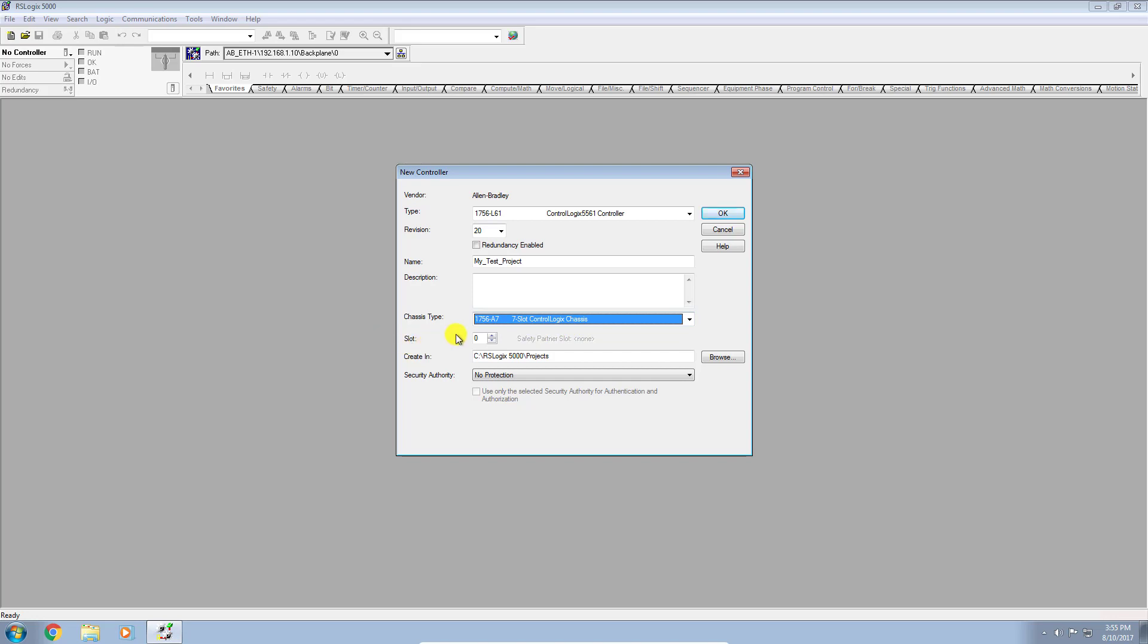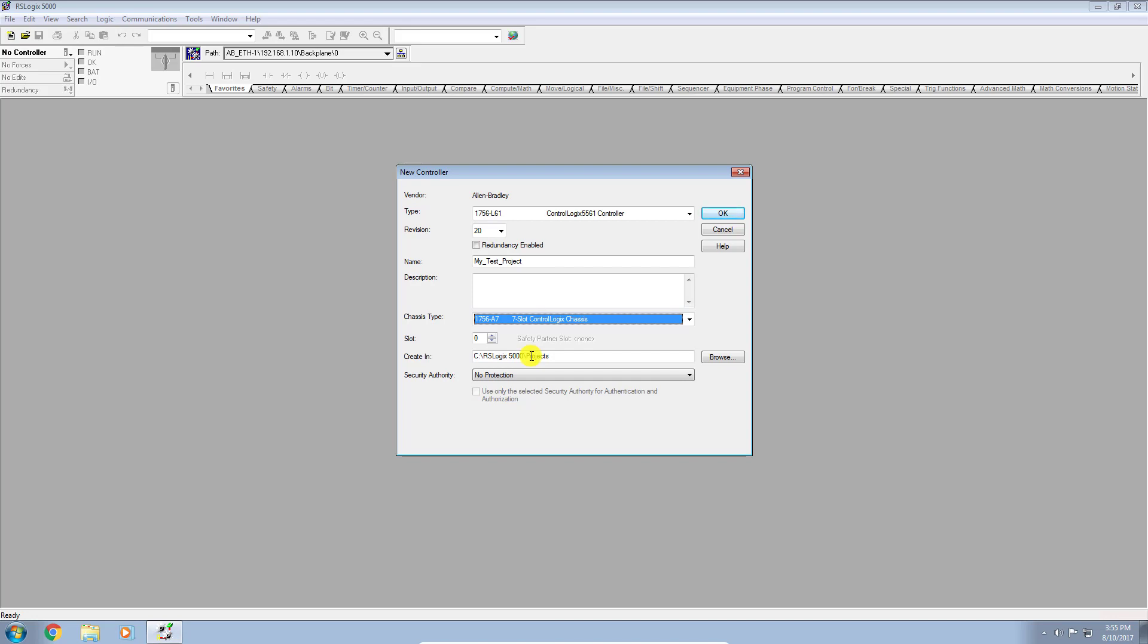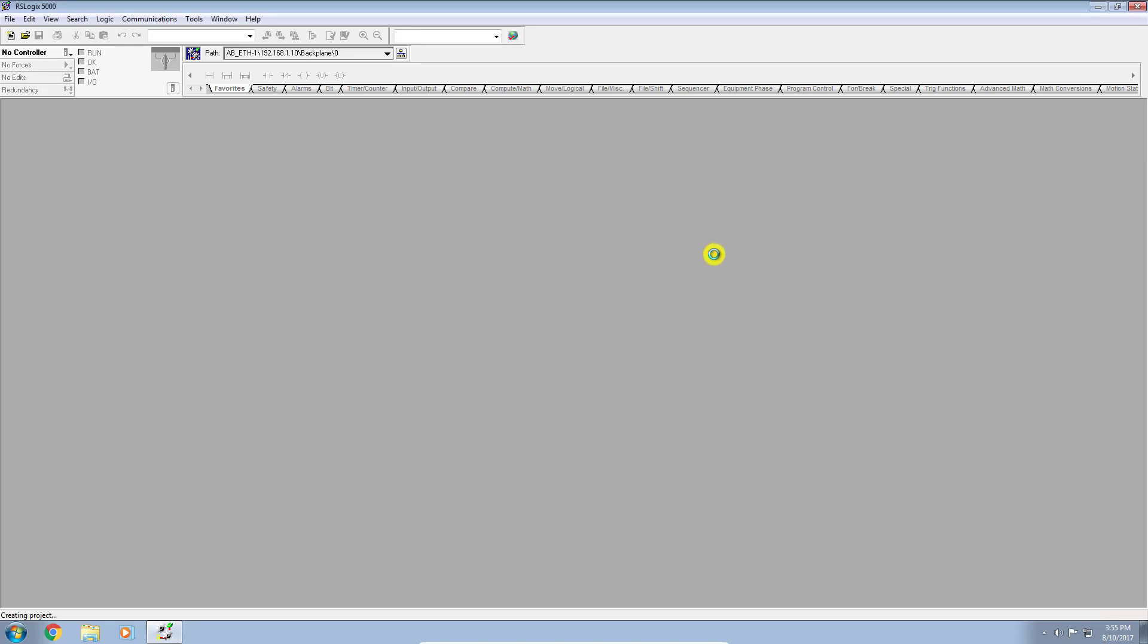So I will select the A7 chassis type here. The slot - this is where you want to tell the software where the CPU physically resides in this chassis. By convention and best practice is slot zero. Now with the ControlLogix platform of controllers, you don't have to put the CPU in slot zero, but by convention, most often you will see it there. Okay, so let's just click OK here.